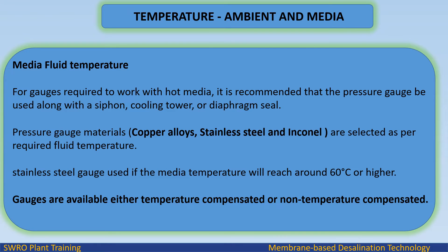Media fluid temperature: For gauges required to work with hot media, it is recommended that the pressure gauge be used along with a siphon, cooling tower, or diaphragm seal. Copper alloys, stainless steel, and Inconel are selected as per the required fluid temperature. A stainless steel gauge is used if the media temperature will reach around 60°C or higher. Gauges are available either temperature compensated or non-temperature compensated.